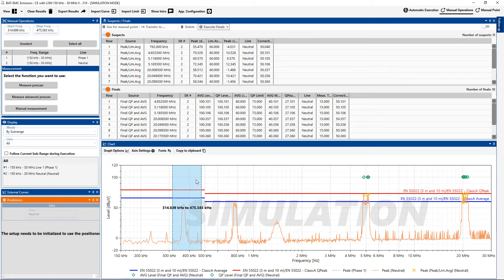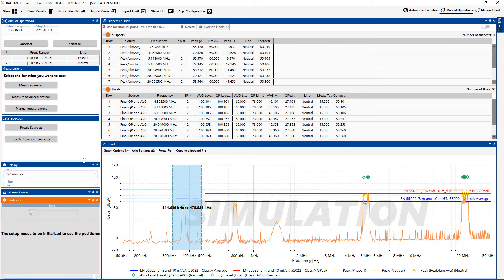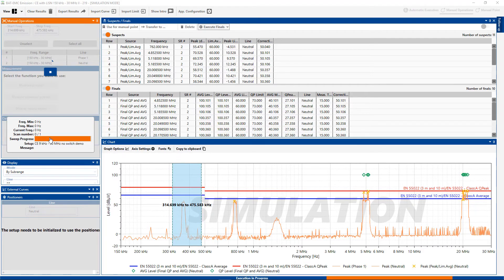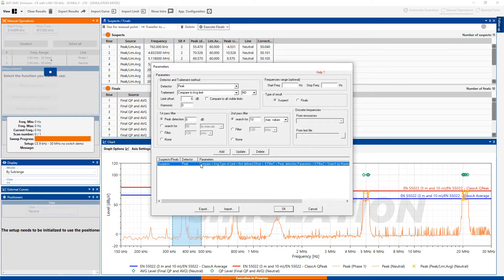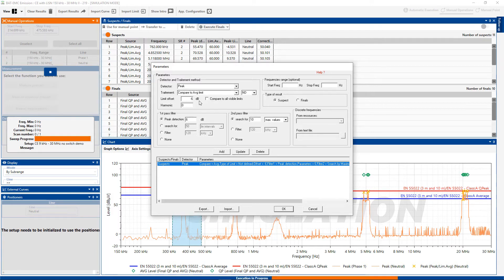Let's say I want to run the suspects on that. Then it's also possible using the data reduction. Recalc advanced suspects. So let's see what we get here. I am going to compare to the average limit line, which is correct. Looking for a 6 dB offset. Okay, that's correct.